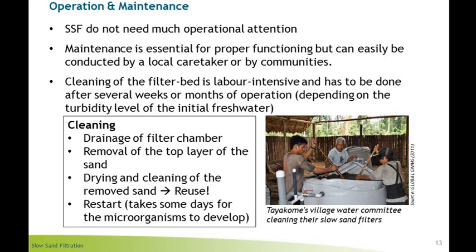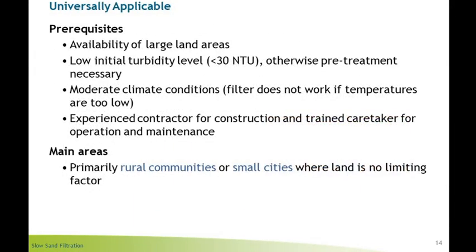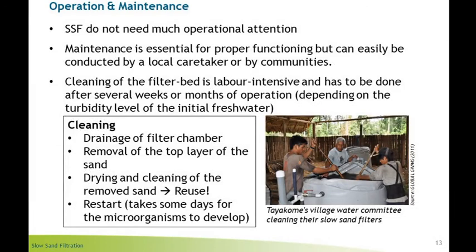To restart your filter again, it takes some days for the microorganisms to develop. So this is about the working of a slow sand filter and how to clean slow sand filters. You can clean by removing the top layer of the sand from that filter and replacing it with new sand, and you can increase the rate of filtration.